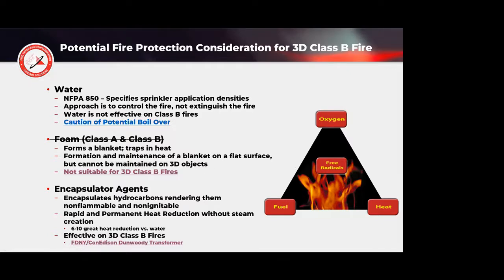I have a whole presentation of a project out in California that took 6 hours to extinguish using foam from crash fire rescue trucks that came from the airport. Well, that's not a function of bad foam, because here in the United States, the FAA has a higher degree of performance for foam. You have to meet the FAA mil spec regulation, which is a higher performance standard than the UL 162. So it wasn't a matter of, geez, we're spraying foam onto a transformer and it's just bad, crappy foam. No, it was high quality foam.